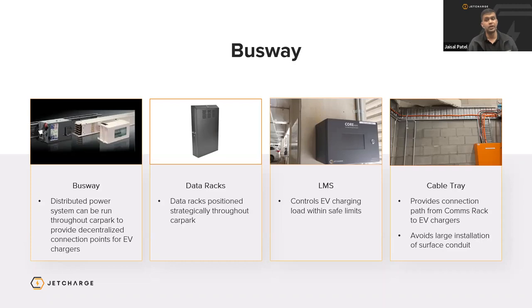The other benefit is that we do not have to run an individual power cable tray. We can just run a singular submains to a feeder unit to the busways, and then the busway runs throughout the entire car park. We have obviously the data rack load management system and cable trays that provide a connection pathway from the comms rack to the EV chargers, because we have to connect the comms rack to the EV chargers to be able to load manage them. And obviously the other point is it avoids the large installation of surface conduit. Next slide.